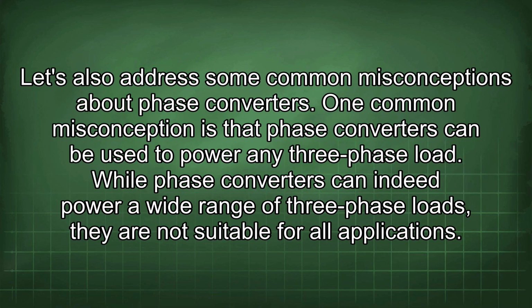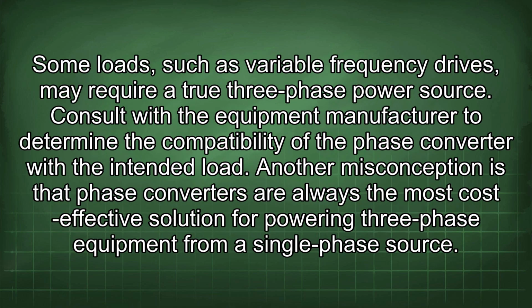Let's also address some common misconceptions about phase converters. One common misconception is that phase converters can be used to power any three-phase load. While phase converters can indeed power a wide range of three-phase loads, they are not suitable for all applications. Some loads, such as variable frequency drives, may require a true three-phase power source. Consult with the equipment manufacturer to determine the compatibility of the phase converter with the intended load.